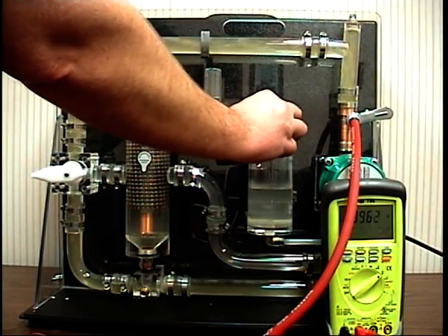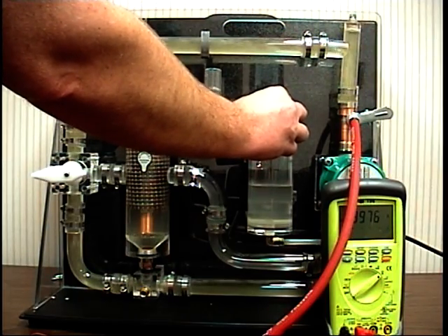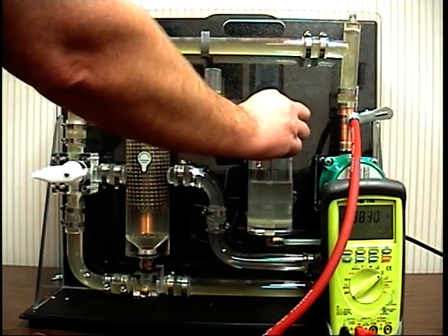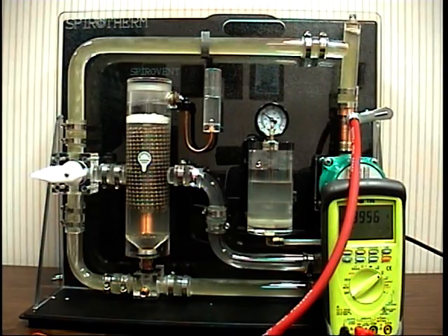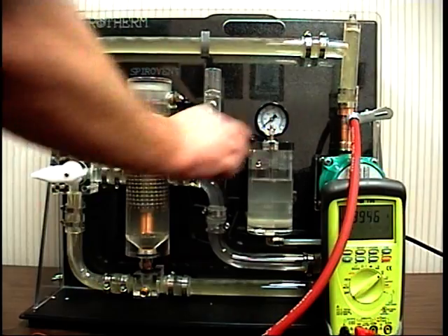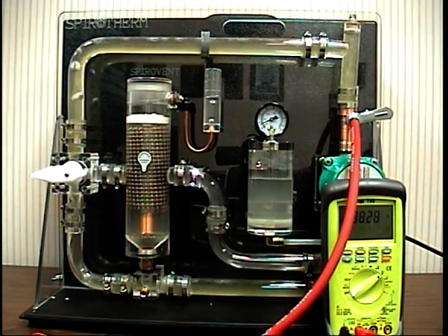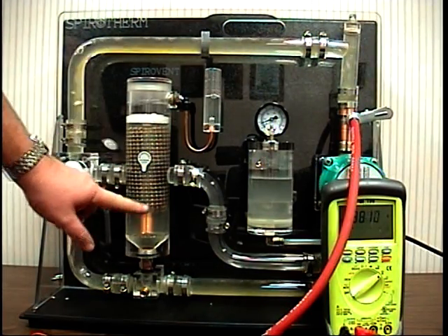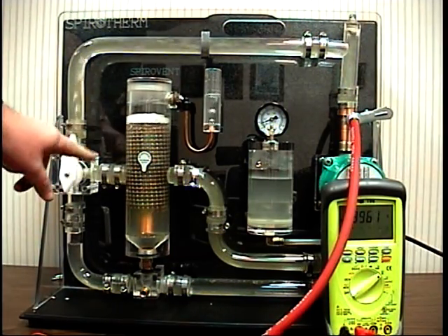If I was to take some of the pressure out of the system, you'd see the bubbles get much larger, almost slowing the flow down to nothing within the system itself, and take the rest of the air out of the system. And now we've almost stopped it. Now, again, watch the air bubbles here at the top being released, and watch also the dirt coming out of the air separator itself. We'll start forcing it through the air separator.